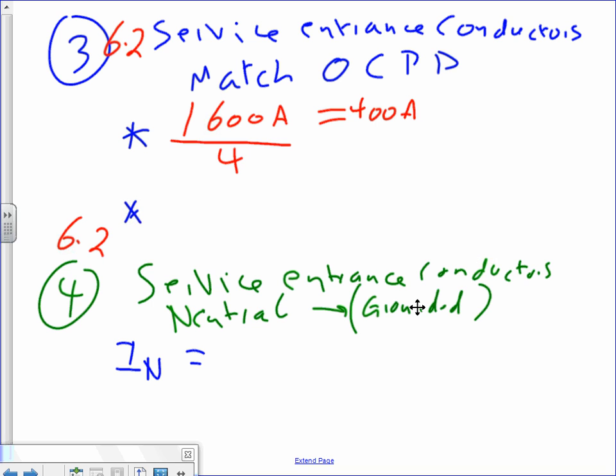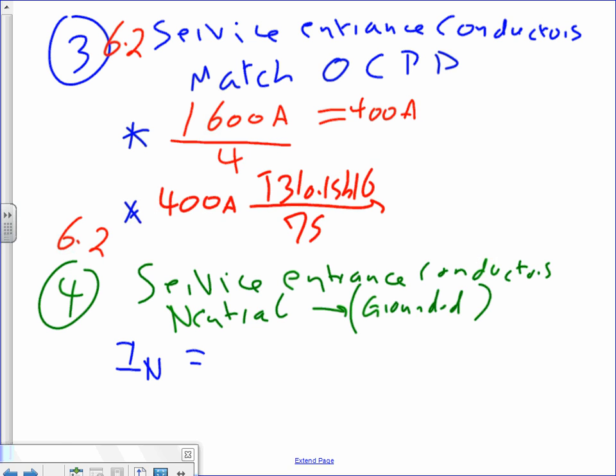Now it's a piece of cake. Now we take the 400 amp and take it to which table? Table 310.15(B)(16), under the 75 degree column. Anybody know why the 75 degree column? Anybody remember that? Well, you always, they're coming from outside. Most likely it will be THHW, which is 75. But it's more than 100 amp. You remember, guys, more than 100 amp, you always default to 75.